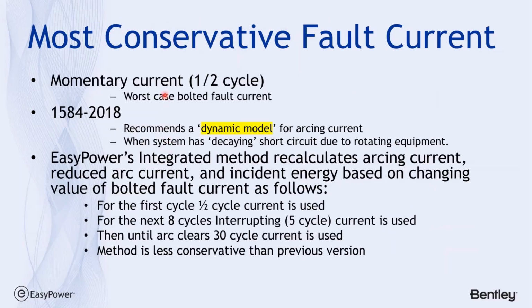Likewise, using the worst case, most conservative fault current. In 2002, the suggestion was to use momentary current because it would be the worst case bolted fault current. However, in 2018, there's a recommendation that we consider a dynamic model for arcing current calculations because the system has decaying current, especially if there's a large motor load or motor contribution, which will decline or decay over a short amount of time. So EasyPower's integrated method recalculates the arcing current for reduced arc current based upon a decreasing or dynamically changing bolted fault current.